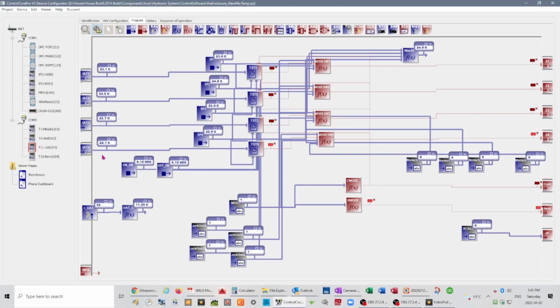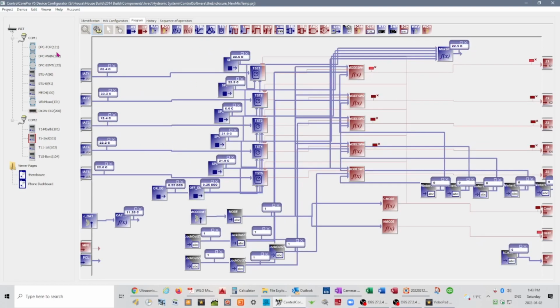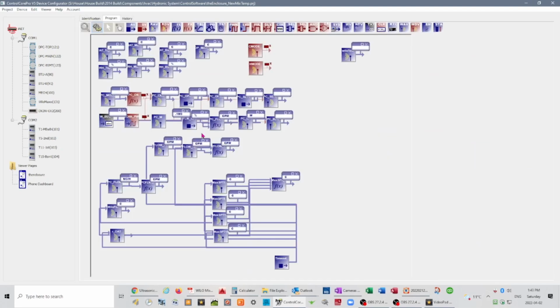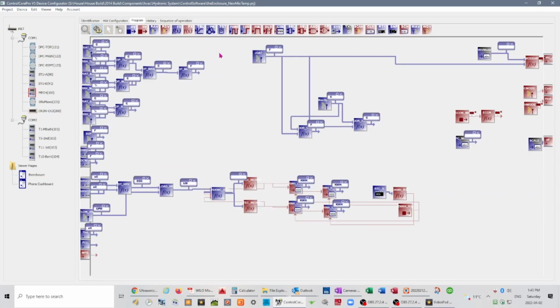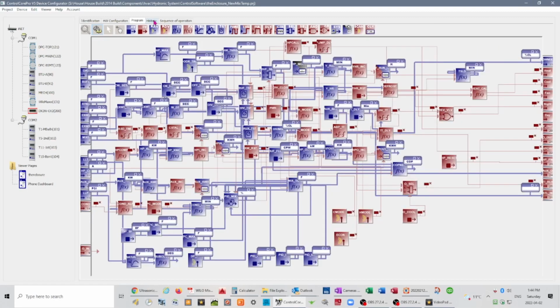We calculate the maximum set point of each iStat. We then calculate the maximum of all of the maximums, and then we use that in the formula to compare with the outdoor air temperature and create a maximum target temperature. And I'll show you why that is so phenomenal. Let's now go to the history.